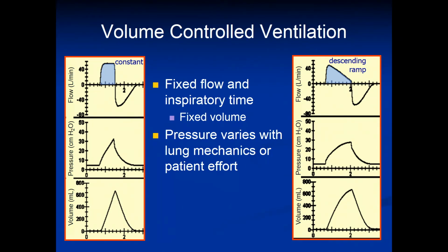An important thing to note that you may be able to appreciate from looking at these graphics is that if you change from one flow pattern to the other without making any other changes to what's set on the ventilator, the time it takes to deliver a breath can be quite different. In this picture, you can see that the inspiratory time is longer with the descending flow pattern. This is something that's very important to consider when changing from one flow method to another.